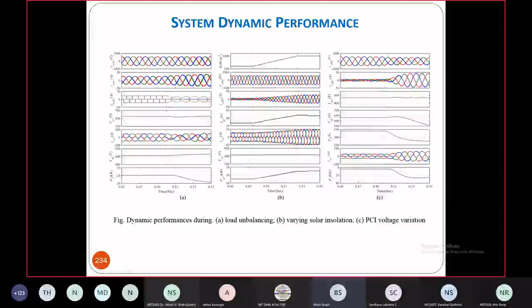Under fault also, a new standard has come that the inverter should remain connected even if there is a fault on the grid, because when the fault is removed, you can bring the inverter quickly into the full control mode. Or if reactive power is needed by the system under that contingency condition, you should be able to provide it by the inverter if required. So all of those are the new standards, and this is the typical result.